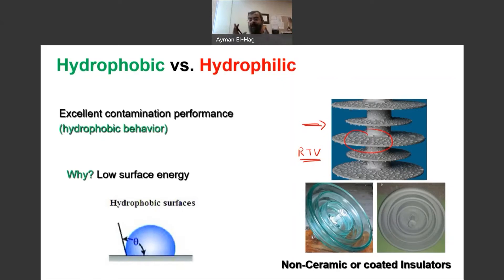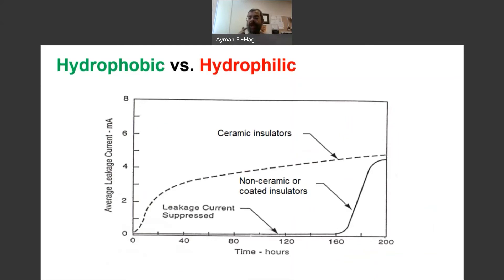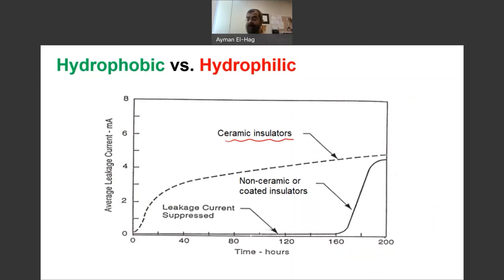And if we have both ceramic and non-ceramic insulators at the same conditions — under the same wetting conditions, at the same high voltage — and we monitor how long it takes for leakage current to start developing on the surface: for the ceramic insulator, it will start almost immediately, because of the hydrophilic nature you will have complete wetting, then the current starts to develop.